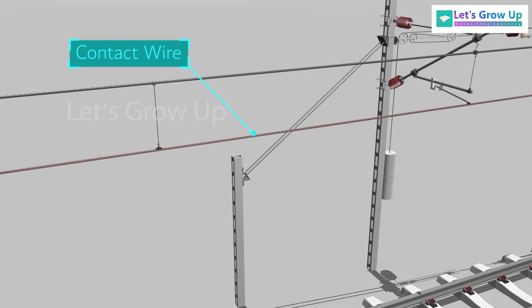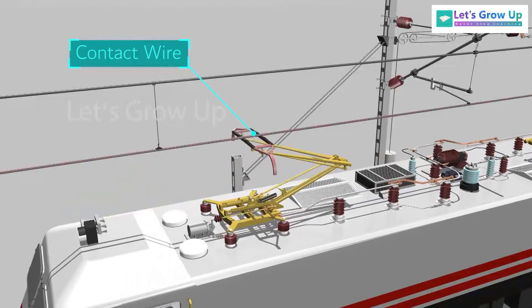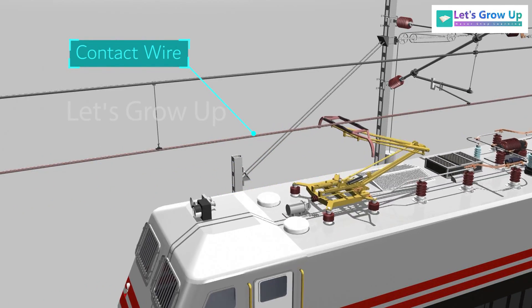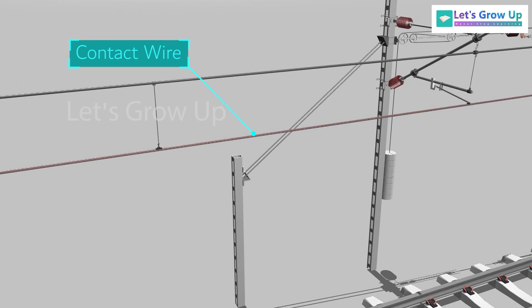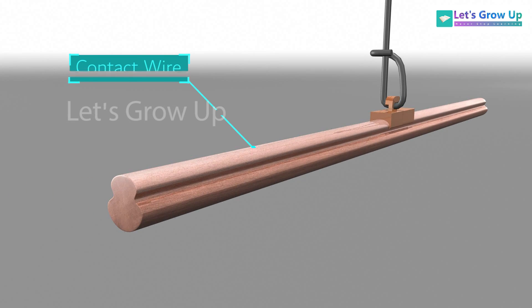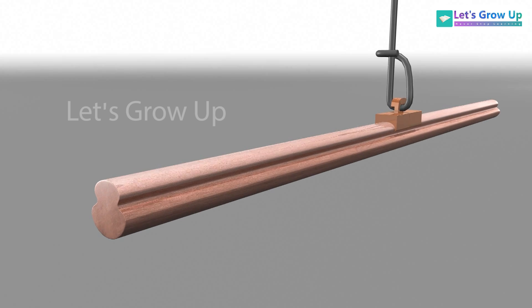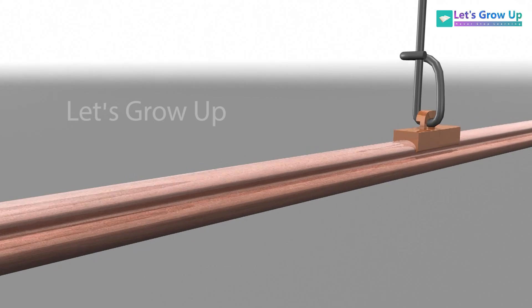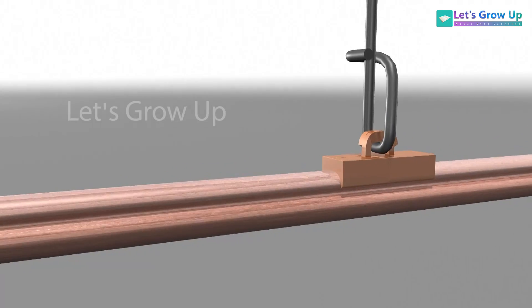This is contact wire. The basic application of contact wire is carrying current for railway traction. Mainly, the contact wire is made from copper or copper alloy with different cross-section areas, from 80 square millimeters to 193 square millimeters in different alloy forms.